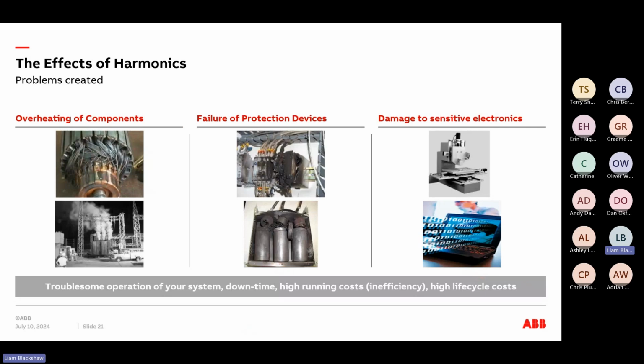So when we look at harmonics and the problems that are created from that, there's a couple of examples there just to name but a few, with some images to go with that, such as the overheating of components, the failure of protection devices, but also damaging sensitive electronics or equipment on that system. Harmonics will increase transformer losses and cause them to overheat over a given period, even without being overloaded relative to their rated data. This could be seen as overheating of the windings, or often as uneven heating of the windings, even though each phase is close to evenly loaded.